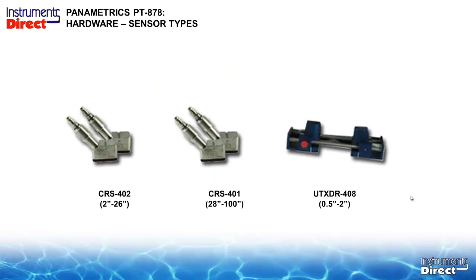It has a host of different transducers. Some of the more popular ones and the newer designs are the 402, which is a 1 megahertz sensor, which is traditionally used from, say, 2 to 26 inches. It can go a little higher, it can't go a little lower. The 401 is a half megahertz transducer. Again, it's designed primarily for larger pipe applications.